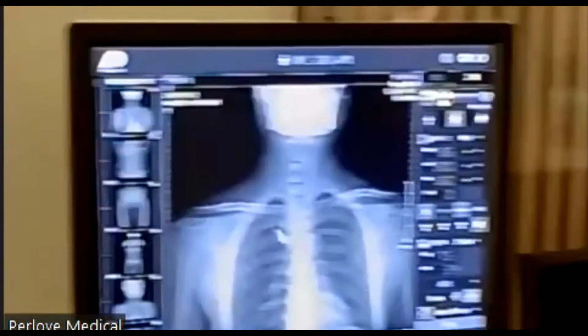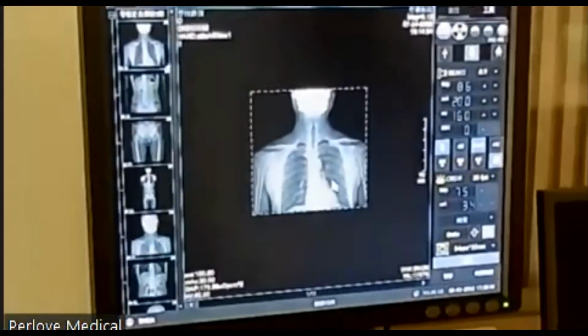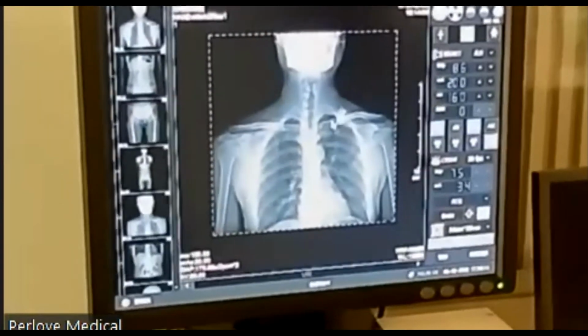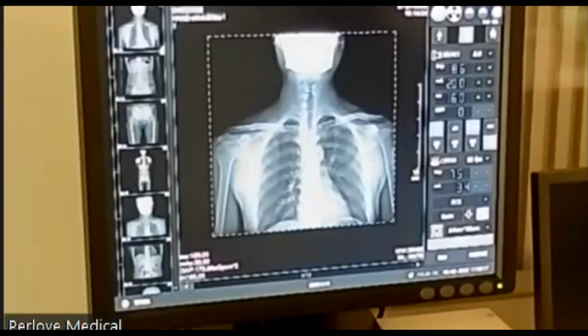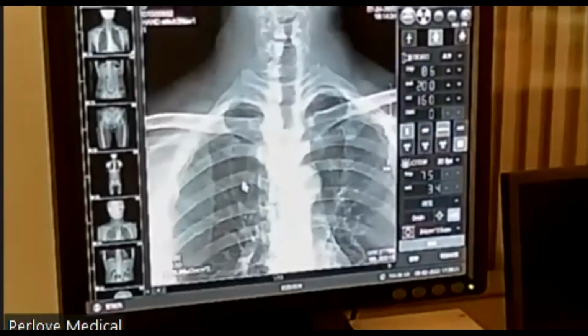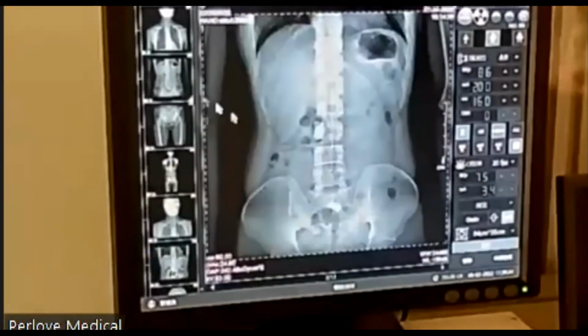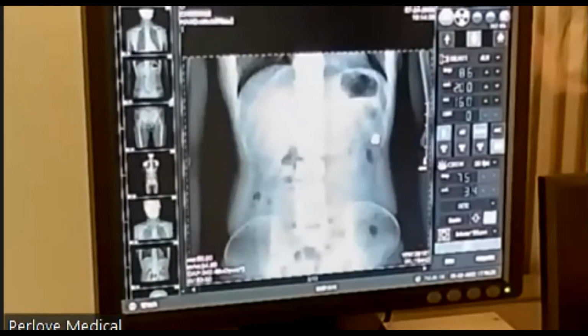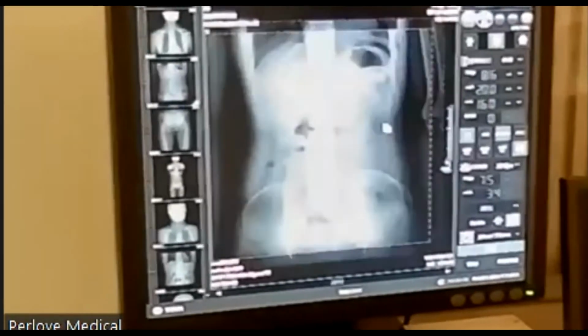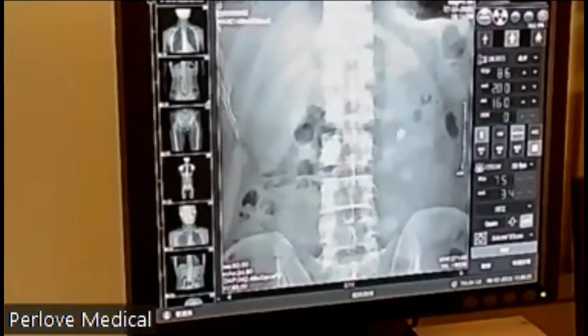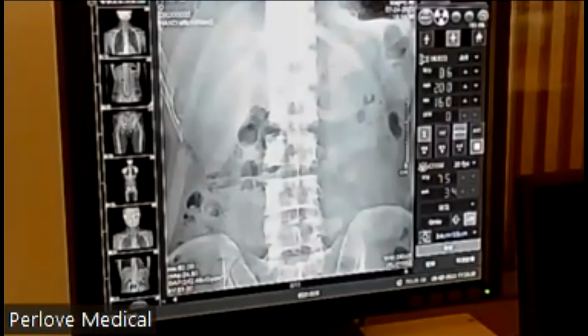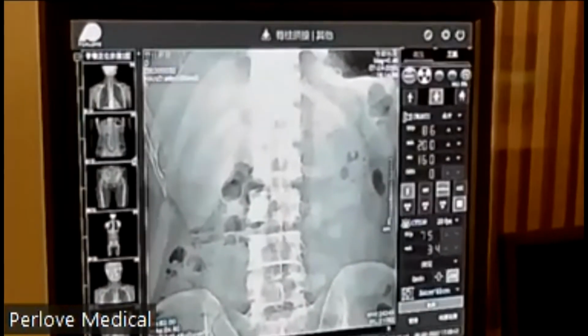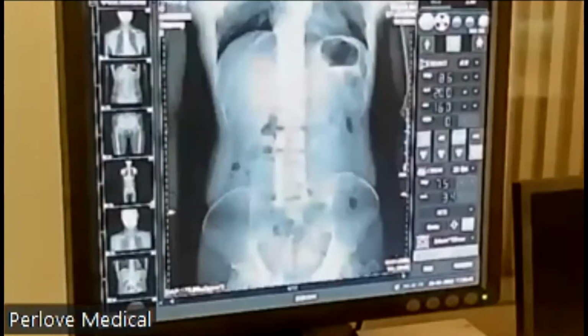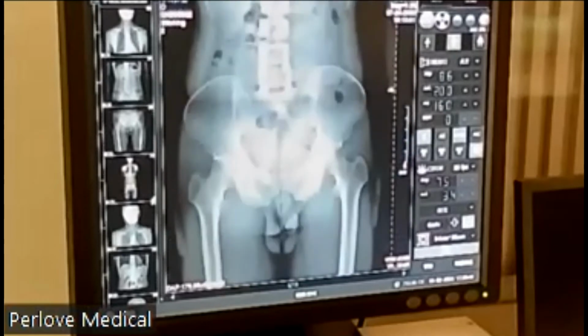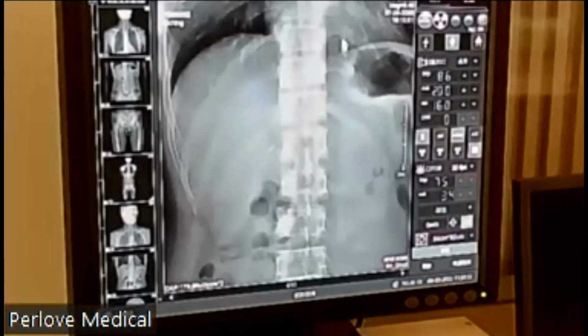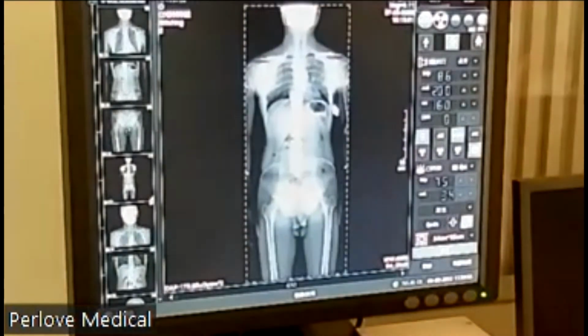Okay, we can see some basic processing tools on the software. Zooming, enlarging. And you can make some marks on the image. Distance measurement, and also you can make digital spot imaging during the fluoroscopy, as it's a dynamic flat panel detector. Of course, another great feature for this machine is the automatic image stitching, as already mentioned. Together with our patient stand, this machine, together with the software, we can make the automatic image stitching to provide you the whole spine imaging and the weight-bearing limb.